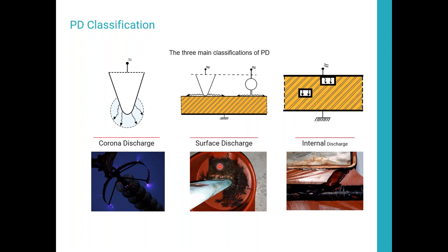Typically caused by a contaminant on the insulation of some form that starts arcing, and it'll keep spreading out until one of these carbon trees reaches a ground point, at which point that's going to arc over. Additionally, you can see on this bus bar section here, this green corrosion being formed.